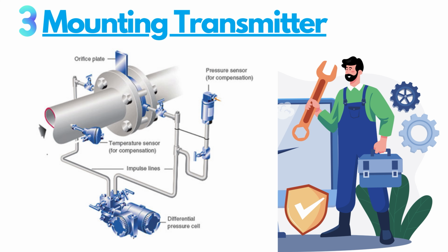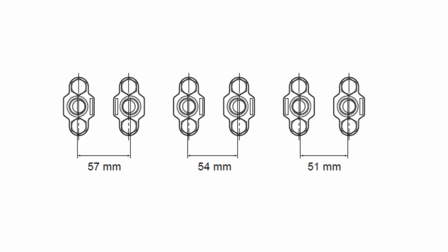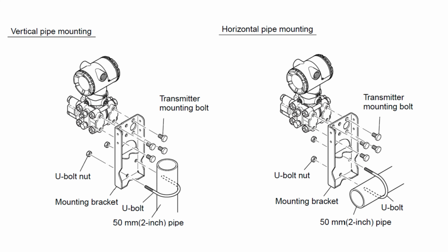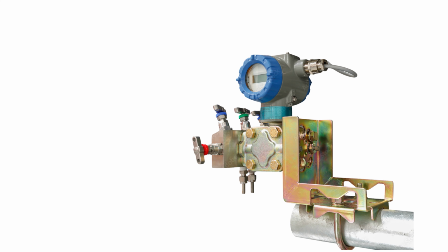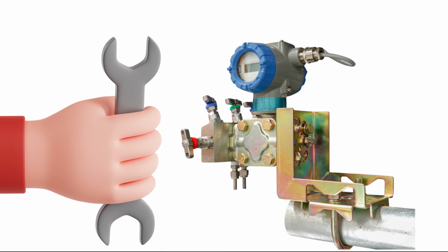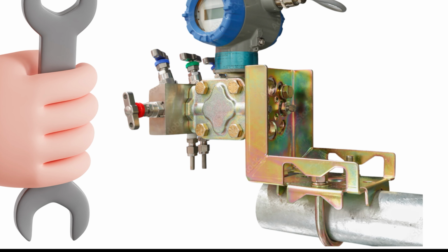Step 3. Mounting the transmitter. Next, mount the transmitter using the appropriate brackets or mounts. The distance between the impulse piping connection ports is usually 54 mm. By changing the orientation of the process connector, the dimension can be changed to 51 mm or 57 mm. The transmitter can be mounted on a nominal 50 mm, 2-inch pipe using the mounting bracket supplied. The transmitter can be mounted on either a horizontal or a vertical pipe. When mounting the bracket on the transmitter, tighten the 4 bolts that hold the transmitter.